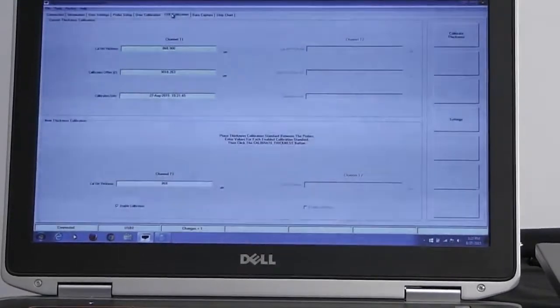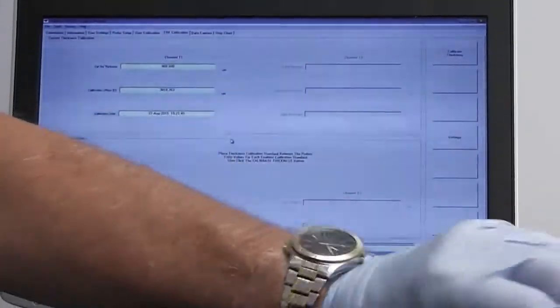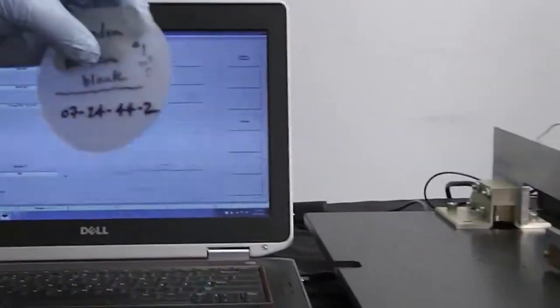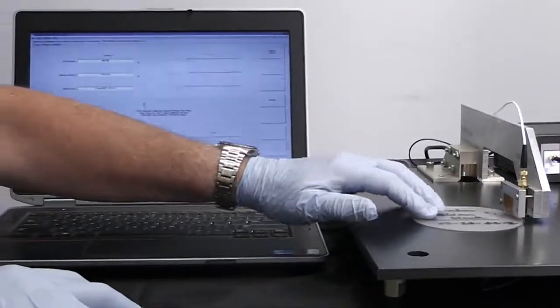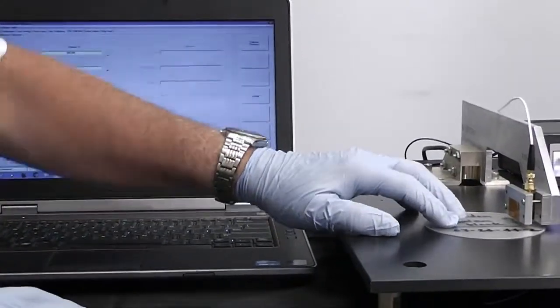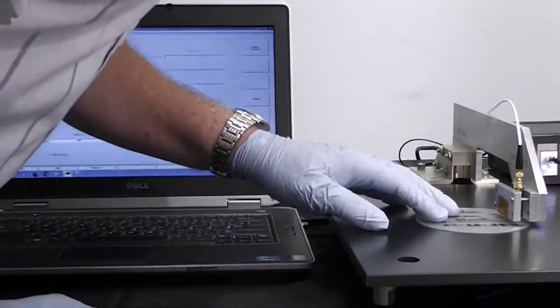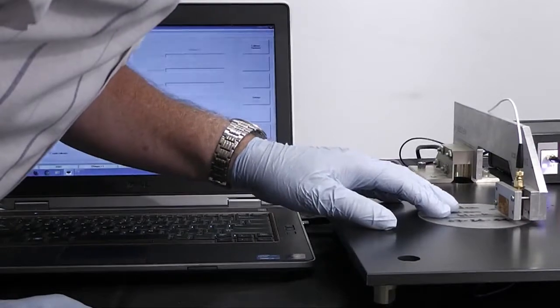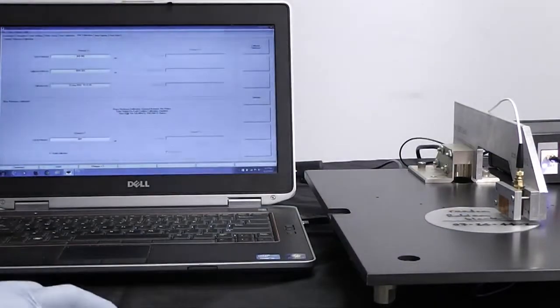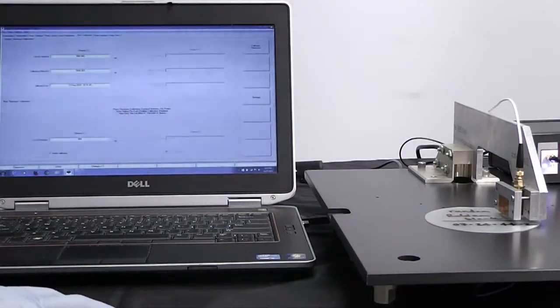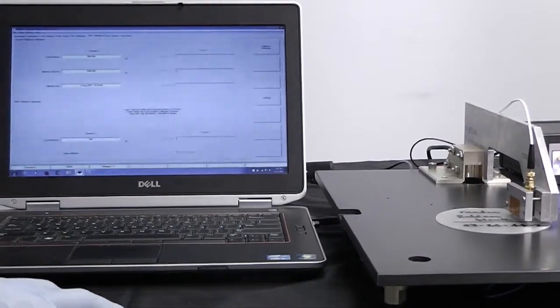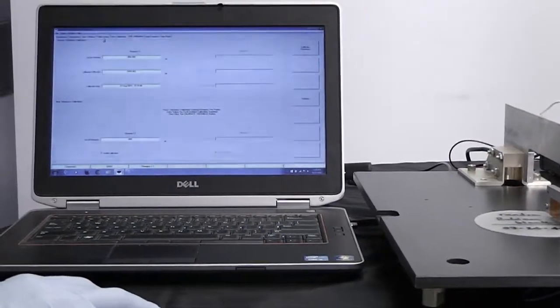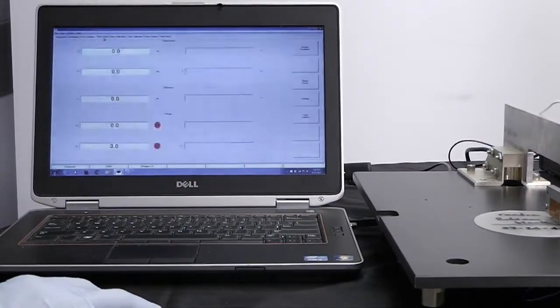We're then going to go back to the thickness calibration window. We're going to put our first wafer which is 868 microns in between the two probes. I've got to make sure I get that centered correctly. And then we're going to hit calibrate thickness. Once we do that, we're all set. We're good to go.